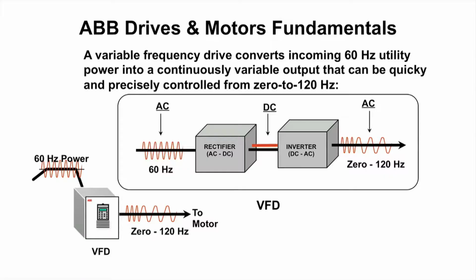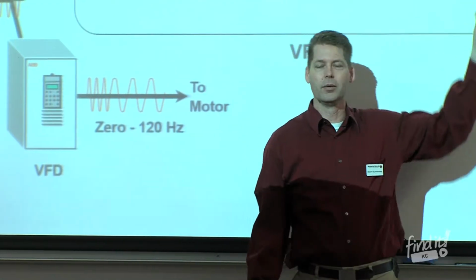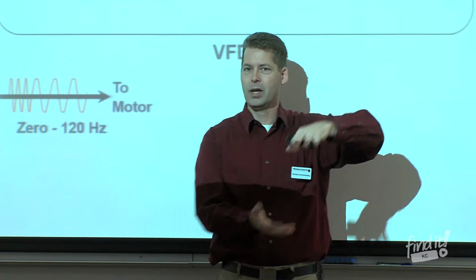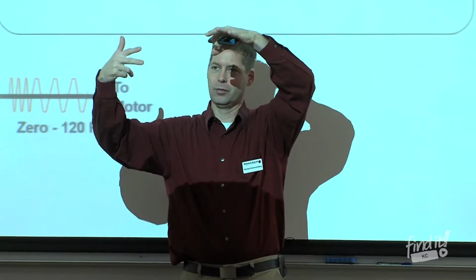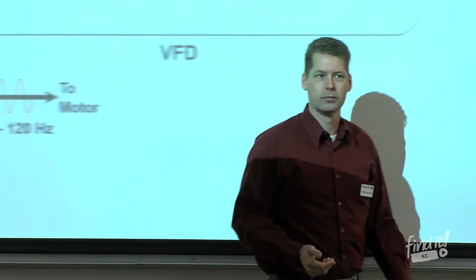You have to derate the drive by half of its current, because on this side, the power coming in, this thing's rated for 10 horsepower at 3-phase power. That's 30 amps essentially. We've got a section here that's rated for 30 amps, but if you take away one of those legs, it still can only handle 30 amps, so it's only going to be able to produce 15 amps on the output side. So that's why you double the size of the drive, so that this side can handle all the amperage necessary to give you the power you want out there. So you'd end up with a 10 horsepower motor, 20 horsepower VFD, and single phase power coming in, and it would work just fine.